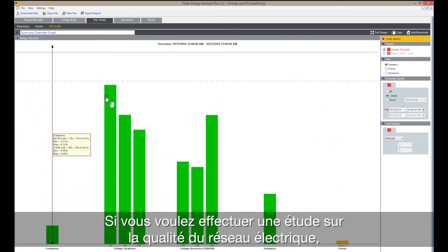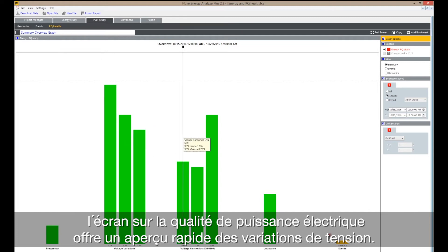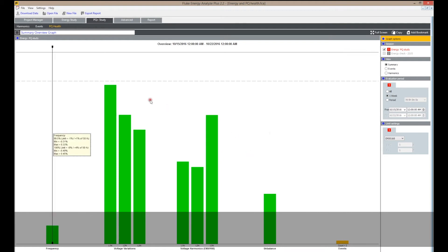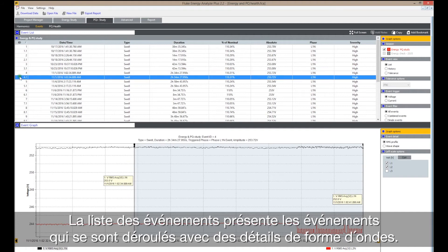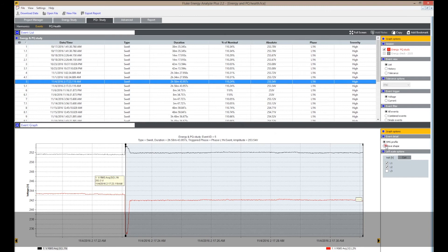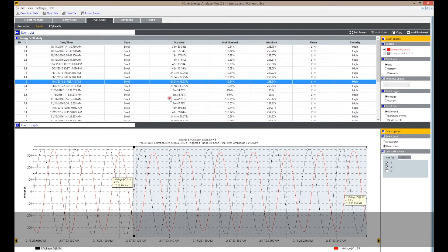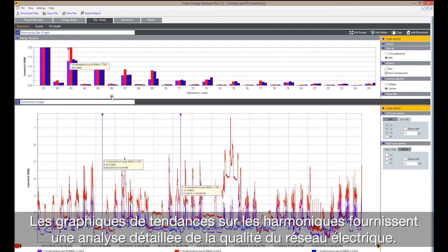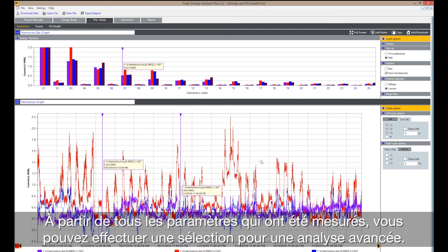If you want to perform a power quality study, PQ Health gives a quick overview about voltage variations with exceedances of limits according to EN 50160. The events list shows the events that took place along with wave shape details. In addition, harmonic spectra are available.